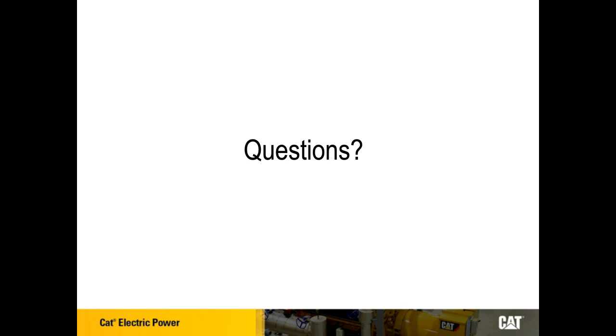It's a great question, Jeff, and the answer is no. Not all Cat gas engines are capable of accepting a 100% step load. Like I mentioned in response to the question about larger gas engines, we have a large number of models optimized for continuous running, whether burning alternative gases like landfill gas or biogas, or running on natural gas for combined heat and power applications. Those generator sets generally cannot accept a 100% block load because they're optimized to be efficient and run a lot of hours with minimal maintenance. However, we have several gas generator sets capable of accepting 100% block load. The largest right now is 1 megawatt. So up to 1 megawatt gas, we can accept 100% block load and also easily parallel those 1 megawatt units together if we need a larger standby power plant.